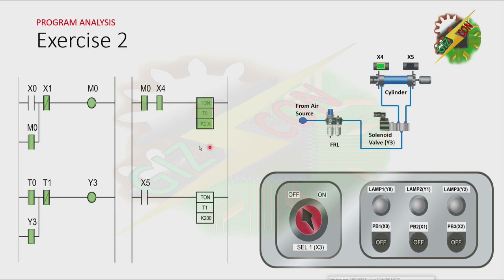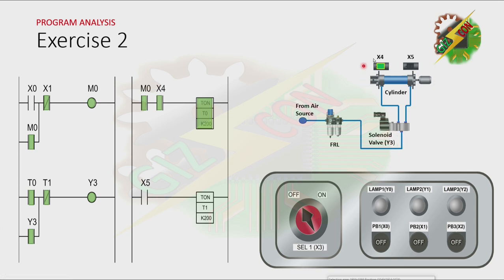And because timer T0 is now on, the normally open contact of T0 will turn on. And that will cause Y3 to turn on. Y3 will not turn off even if T0 is off, because there is a latching here. And because Y3 is on, the solenoid will turn on. And that will cause the cylinder to extend.